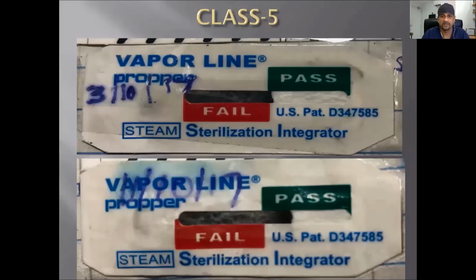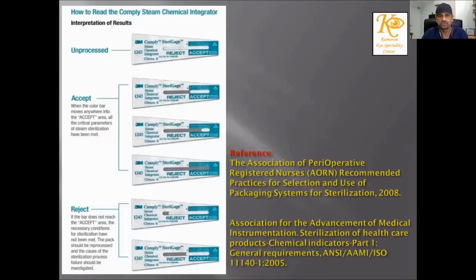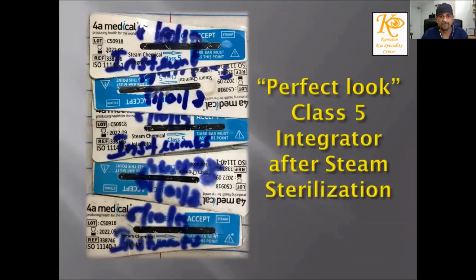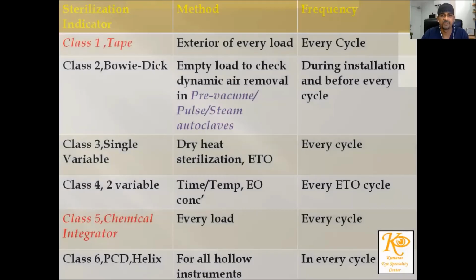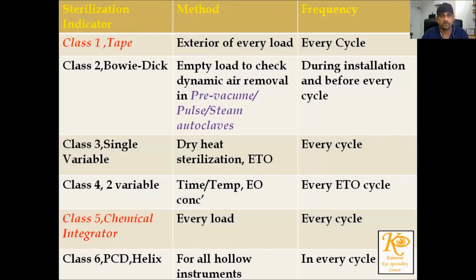The class 5 indicator is equivalent to the biological indicator, and once the chemical indicator inside a class 5 crosses the center stage, then it can be used. The manufacturer guidelines indicate that once the indicator crosses the center, it can be used. So this is the perfect look of the class 5 indicator. And this is the tabular column of what kind of indicators have to be used in different cycles.